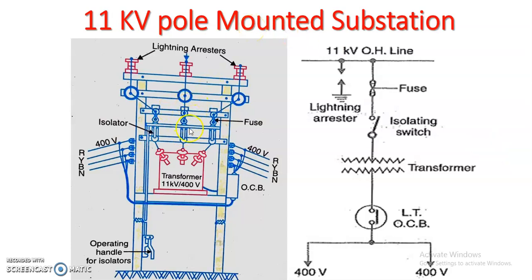The first figure indicates the layout of the pole mounted substation and the second figure shows the single line diagram of the 11 kV pole mounted substation. In this diagram we see the lightning arrestor is located at the top of the substation, and the incoming 11 kV line is connected at the top through the fuses and gang isolator. It is connected to the HV winding, that is the 11 kV side of this step down transformer.